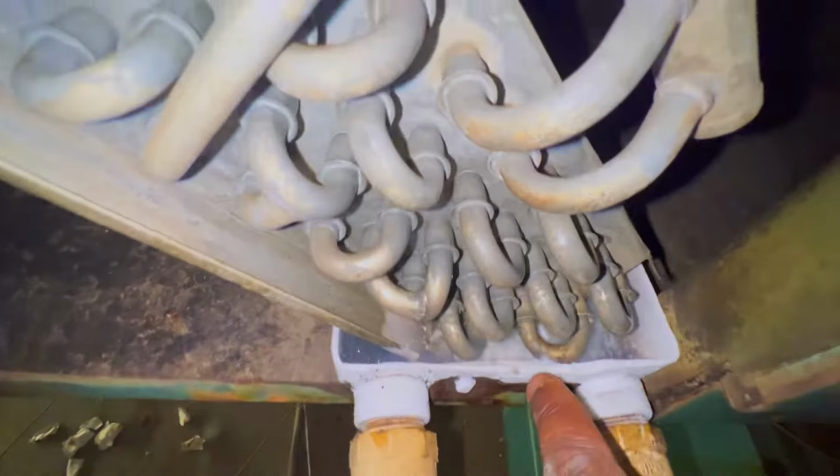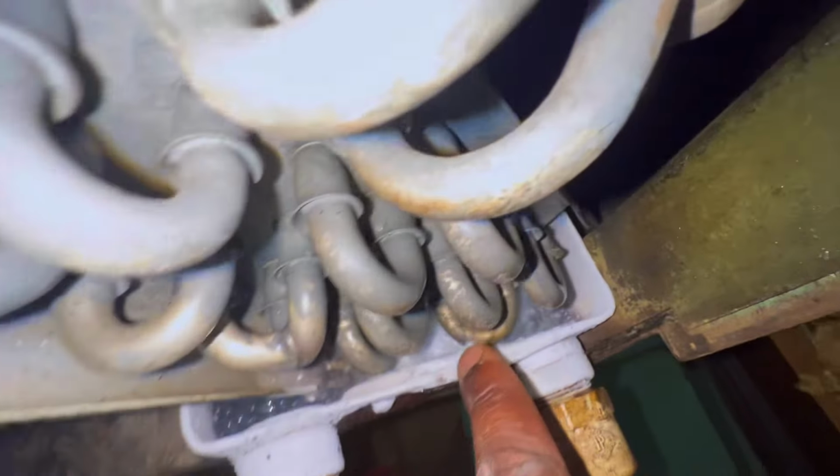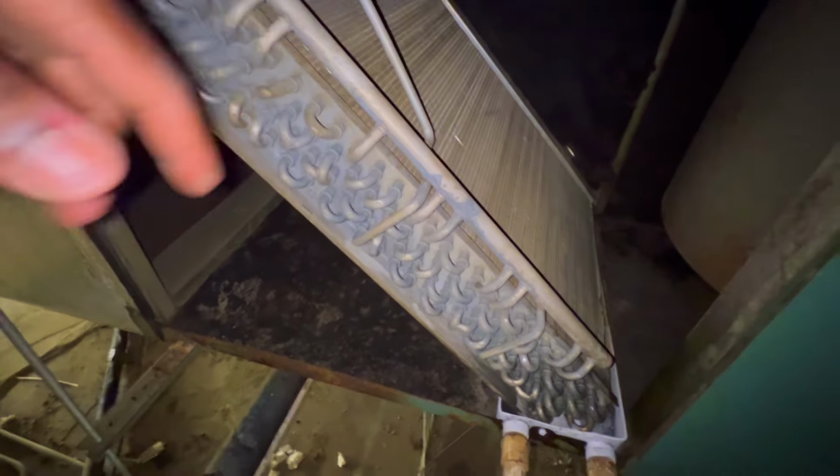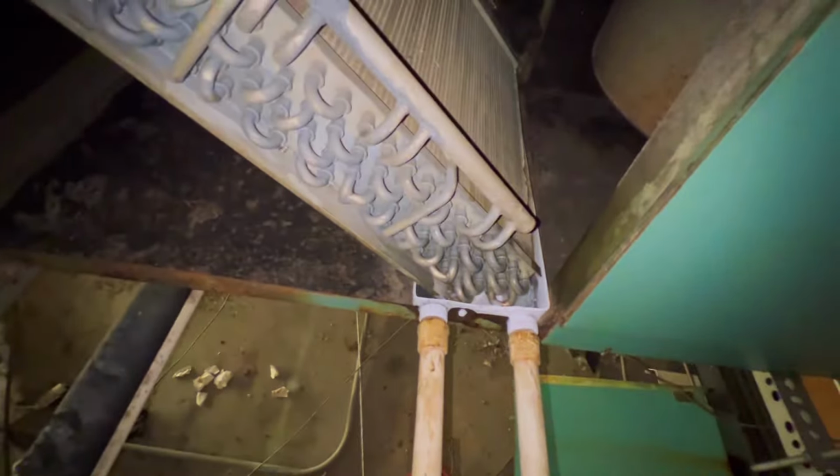So to me, it looked like it had rub on there over time. So it's good, I guess, to do preventative maintenance. It's kind of crazy because I checked this unit last time and I leak checked, didn't get no leaks, pressures were in range.